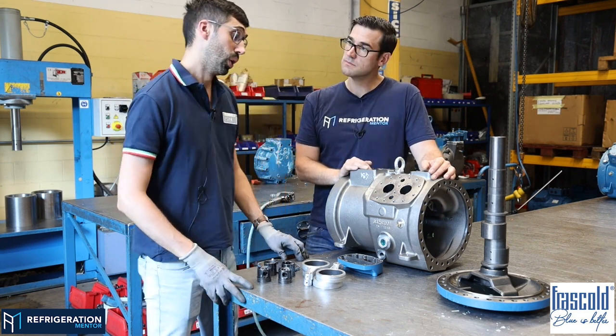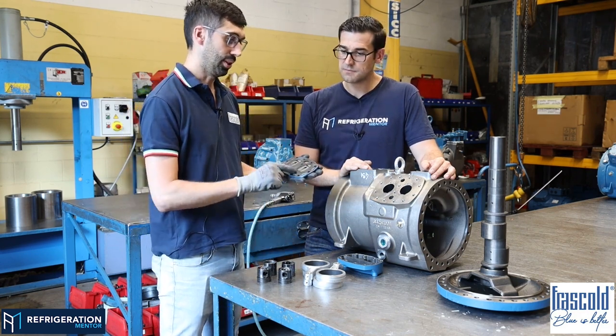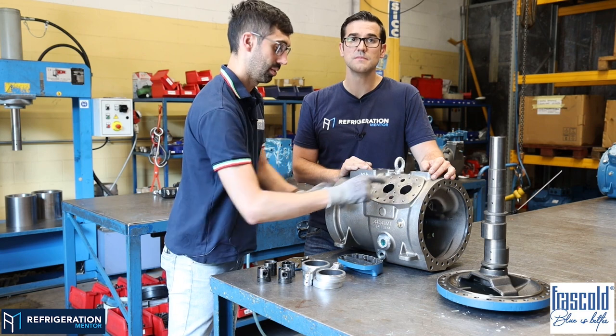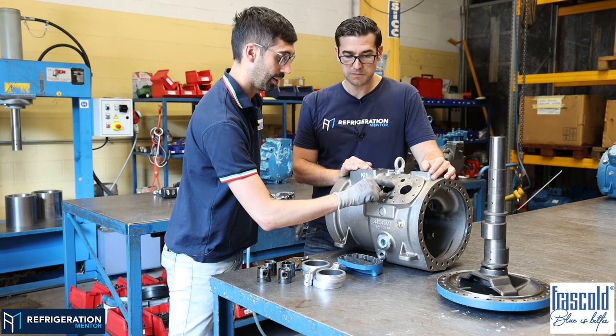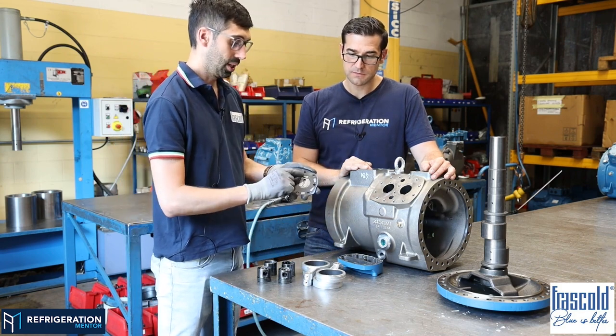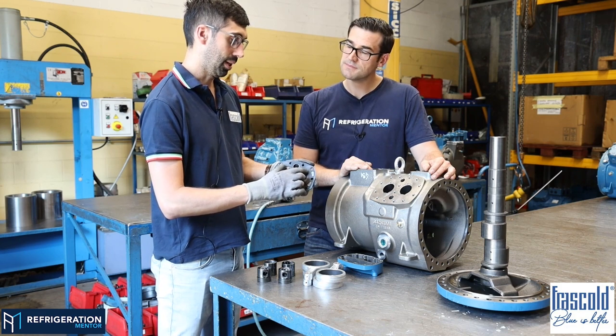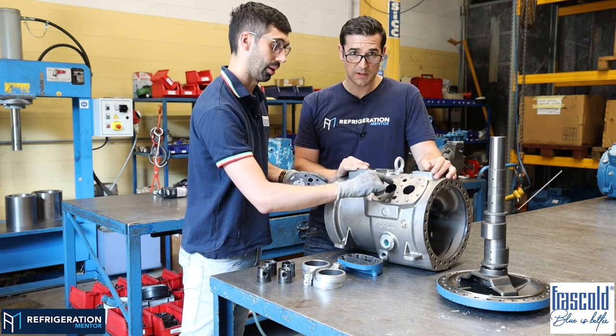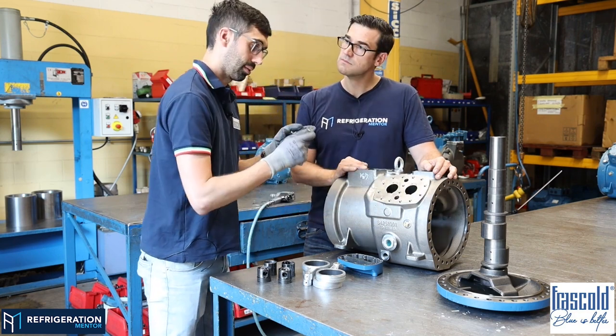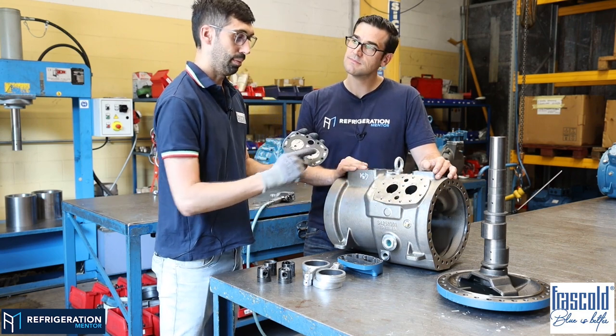The process is to go step by step from the bottom to the top and see the shape of the gasket and be sure that it matches this perimeter. And then you put the valve plate. The valve plate usually has pins. You can have 4 or 8 pins that can be inserted in the proper little holes. So in the end, be sure that you are reaching plane-on-plane coupling because you have centered the pins with the holes.